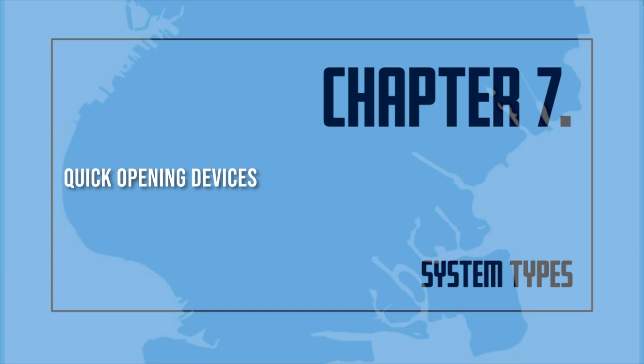Quick opening devices. In a dry pipe system, there is a delay between the opening of a sprinkler and the discharge of water. This delay may allow the fire to spread and more sprinkler heads to open. The delay is due to the time required for the air to leave the sprinkler piping. This difficulty may be partly overcome by the installation of quick opening devices. Two devices are used to reduce the time needed to open the clapper and allow water into the system. These devices are an accelerator and an exhauster.